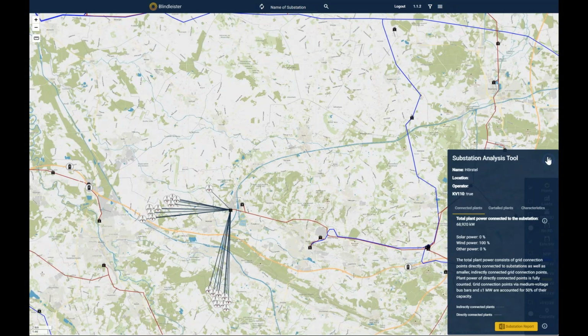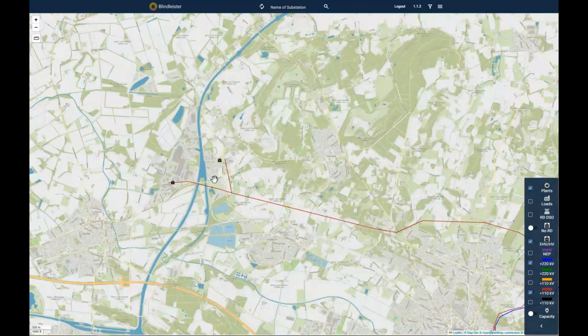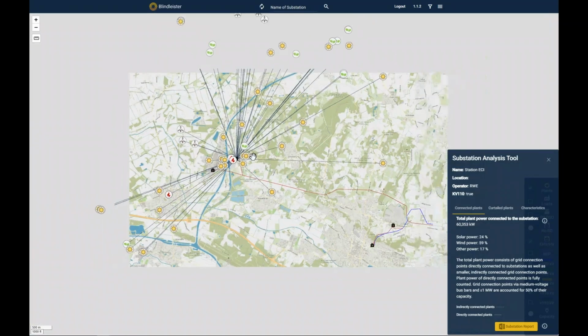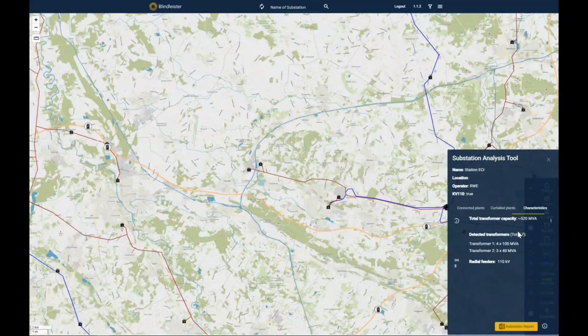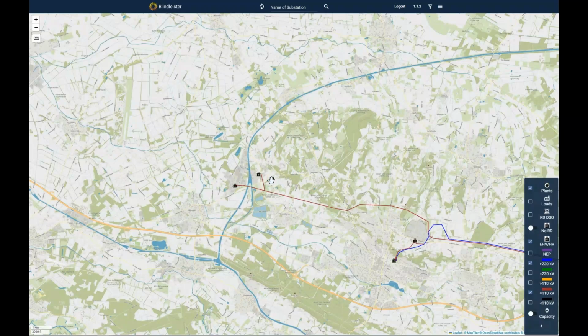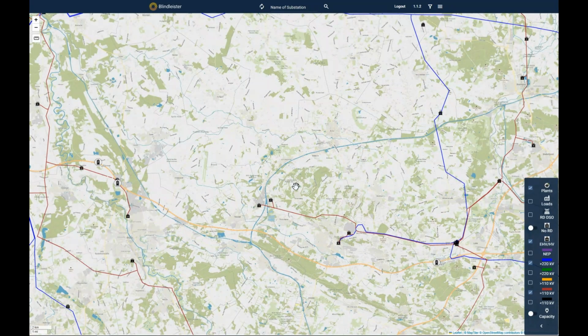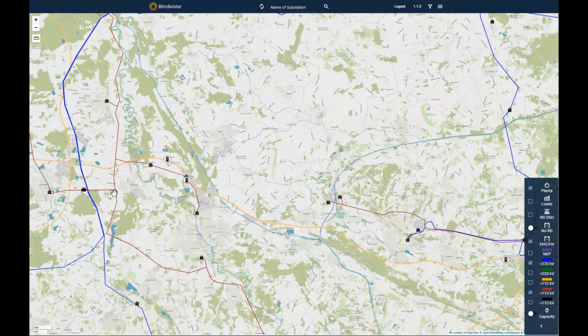So what's important here? When we go a little bit deeper, we see that there seems to be a lot of transformers. This is also because it's a load center and we have to fulfill the N-1 criteria. And we also see these are two radial feeders, which means there is only one line leaving this kind of area here, which means that it's not meshed. A meshed area is something like this substation here, for example, and the line goes here and the line goes here and it splits up again.